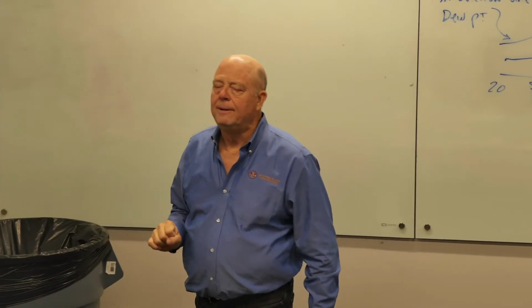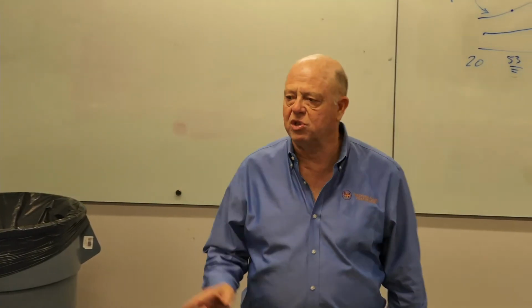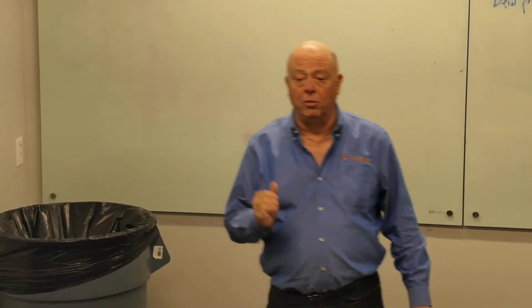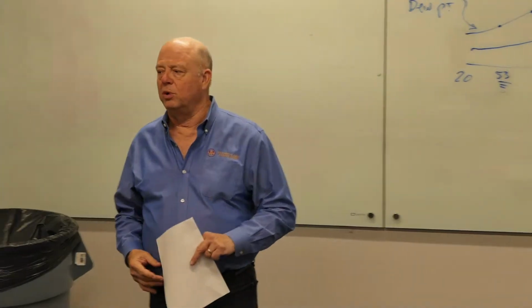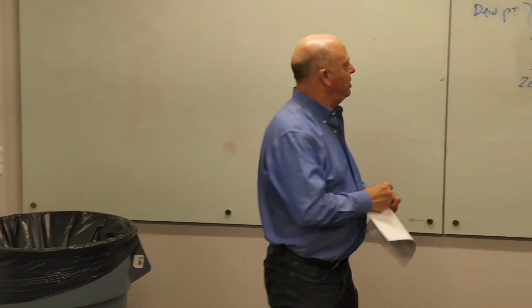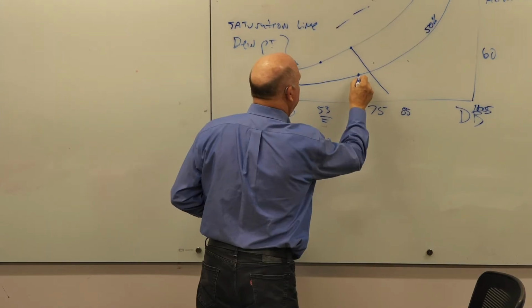This is rigid. I think I told you guys at some point in the past that the state of California started, instead of inspecting every 3 years, like 15, 20 years ago, they give you a call and 45 minutes later they show up. Have you gone through that? Yes, I'm seeing some nods. One of the things they look at as soon as they show up is, take me to your operating room. What's the relative humidity in there? So they do monitor that now. You will not find a charge nurse on a surgery suite floor that is not looking at relative humidity. So let's talk about what that means in the real world. Most of these rooms were designed for something like 70 degrees and 50% relative humidity.